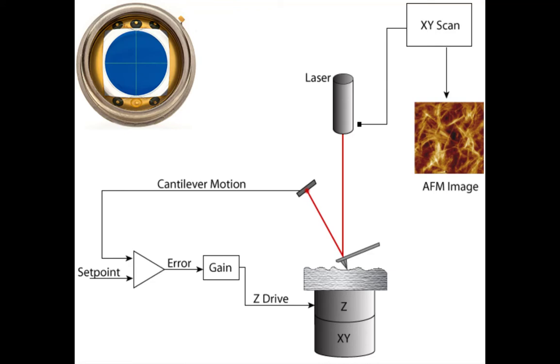The photo detector that we have on ours is a four quadrant detector as seen in the top left. And upon starting this analysis we will center the laser on all four quadrants in the very center so that any deflection the laser has we can measure it with high sensitivity.